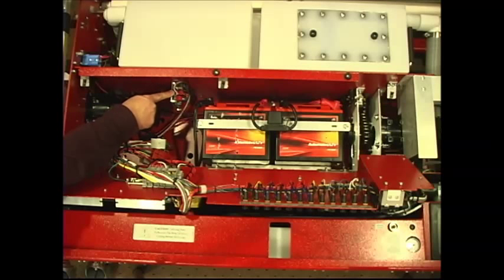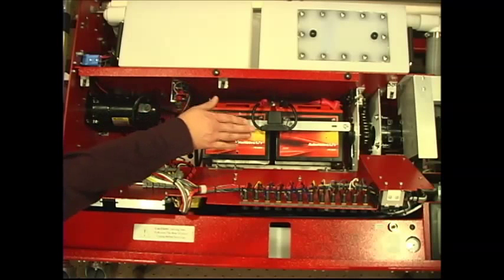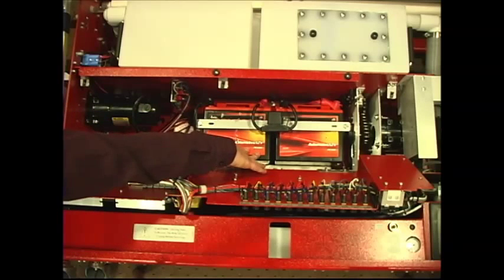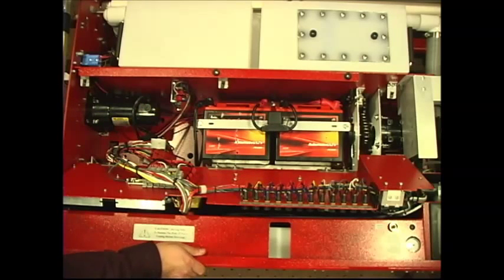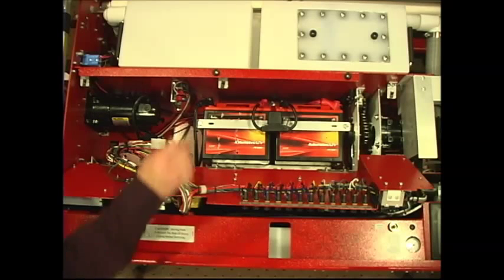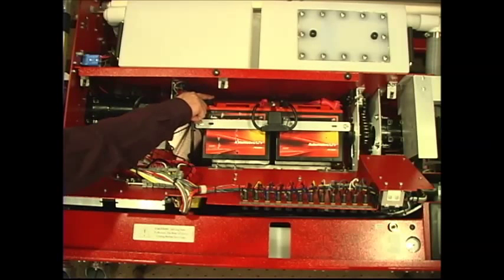This is the CVR, which stands for Constant Voltage Regulator. What this does, this will allow the machine to continually run at 26.2 volts even while the batteries are discharging. Here's your 2 Odyssey batteries. Depending on the size of the center, you'll either have Odyssey 1200s or Odyssey 925s. It's very important that you always check the battery connections.